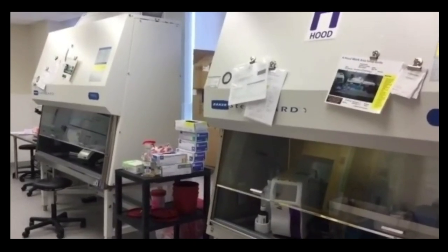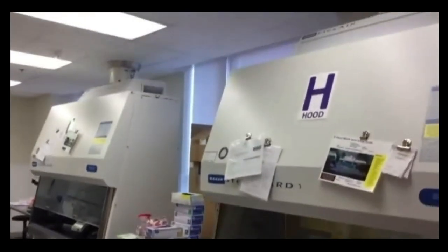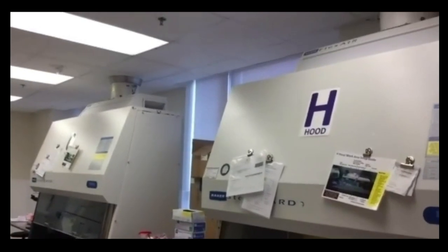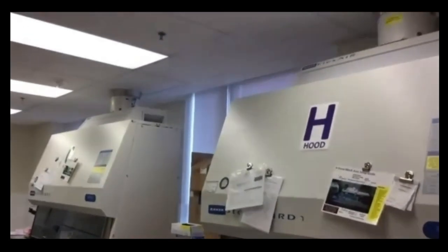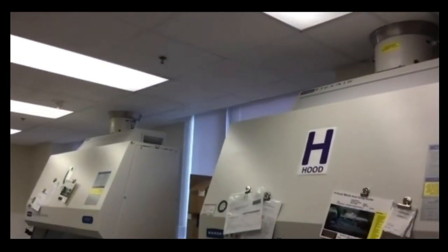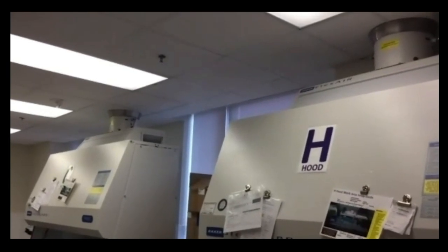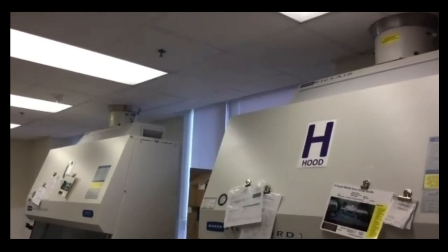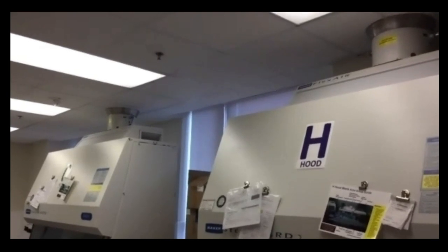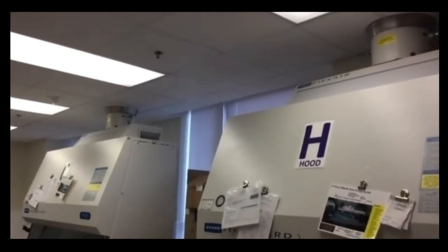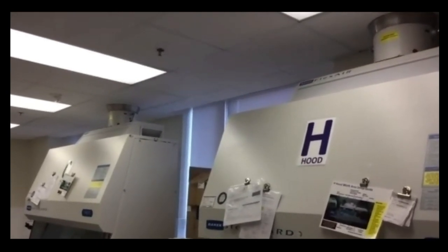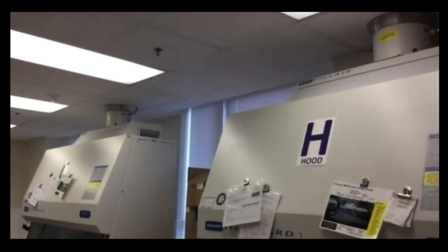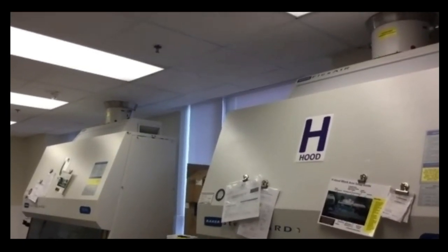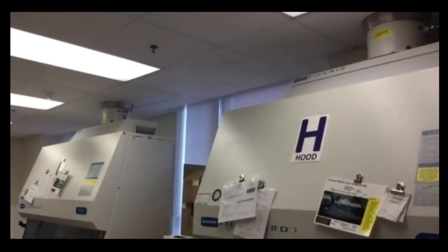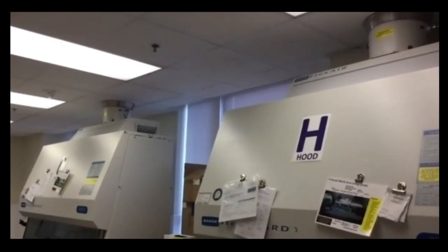If you look up at the top of the hoods, you can see that they connect in through chimneys into the air handling system of the unit. So the entire unit is negative pressure relative to the regular hospital. All of the air intake is specially filtered on the way in, and on the way out it's filtered through two fan banks on the roof with HEPA filtration, the highest efficiency filtration we have. Each of those fans can operate the entire unit, so we can do maintenance on one fan and still maintain the unit.